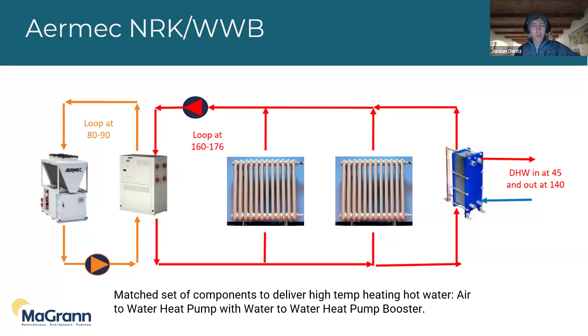We need higher temperature water, and so there's a 2-stage system, or a cascading heat pump system with a booster in the middle that's boosting it. It's a water-to-water heat pump that boosts the water from that 80 to 90 up to 176 for delivery to the terminal units.